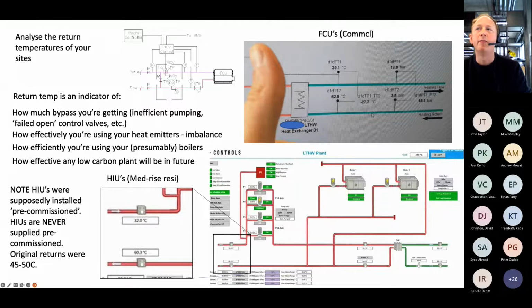So it's a lovely rule of thumb really to know what your system should be returning at its design temperature. For a mixed constant temperature, variable temperature system, it's a little bit hit and miss, but by switching to a fully constant temperature system, you can get an extremely useful KPI to trend, one which waves a big red flag when something's not right. It's like a big check engine light on your BMS.